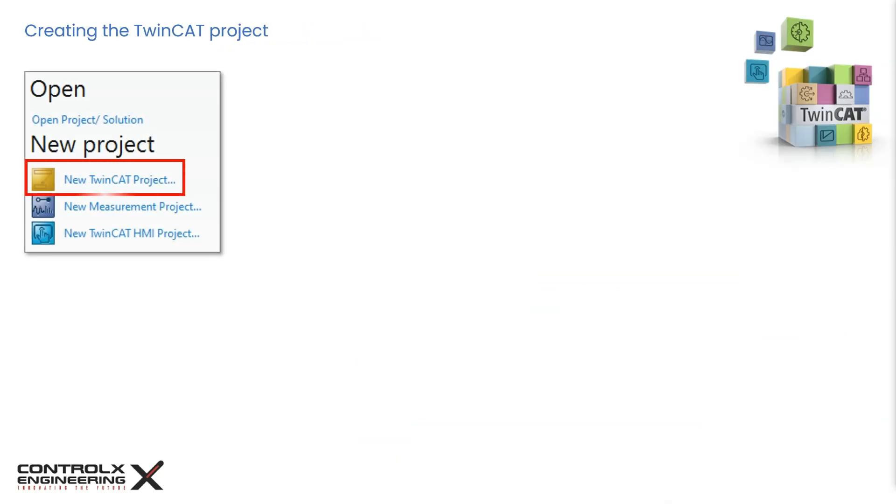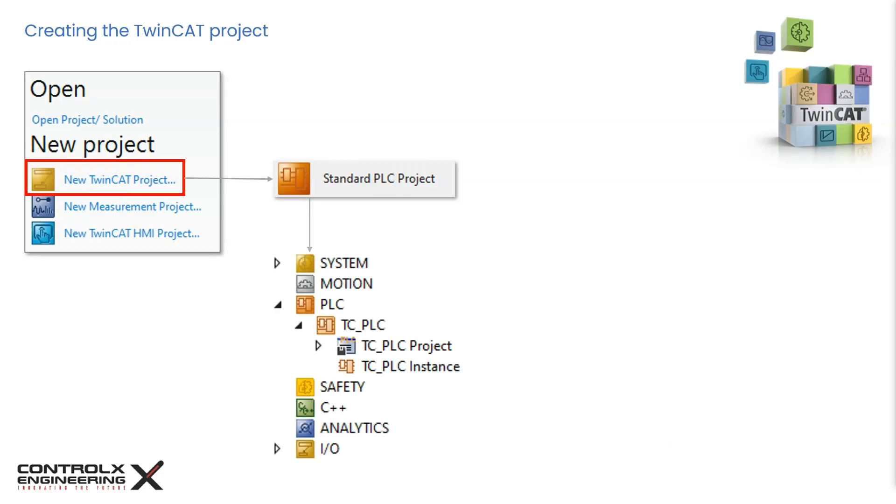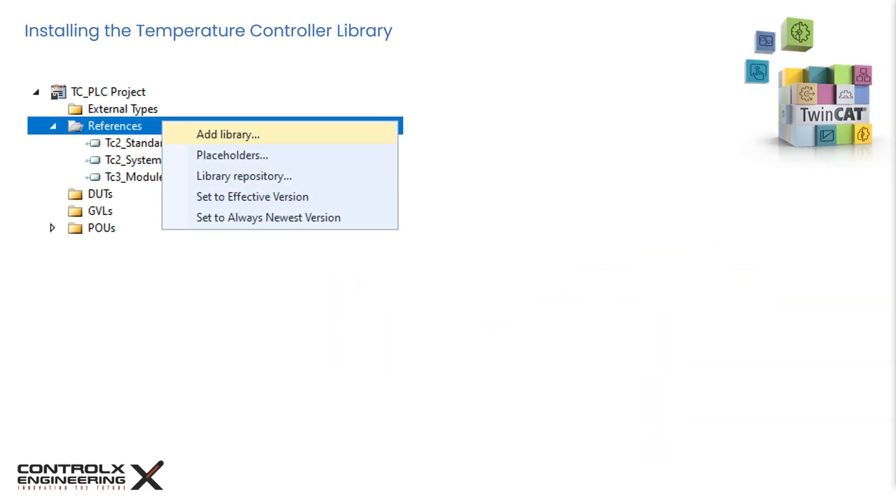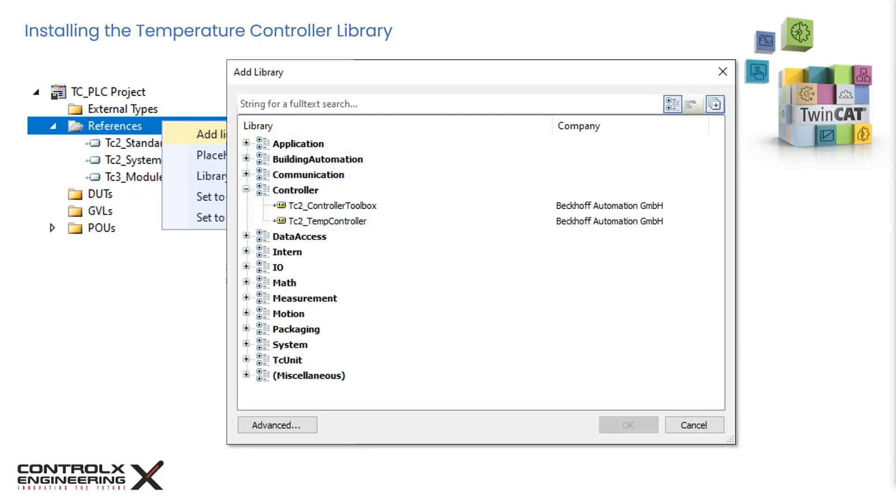Let's open TwinCAT and start a new TwinCAT project. Add a new PLC project and select standard PLC project. Give it an appropriate name. I'll call mine TC_PLC. This adds the PLC project to our solution. Expand the project part and navigate to references. This is where we'll add the library for the TF4110 that we had installed using the downloaded executable file. Right-click on references and select add library. This will open the library dialog box. Navigate to controller and install both the TC2 temperature controller and the TC2 controller toolbox libraries one at a time. The two libraries should now show up in your references.